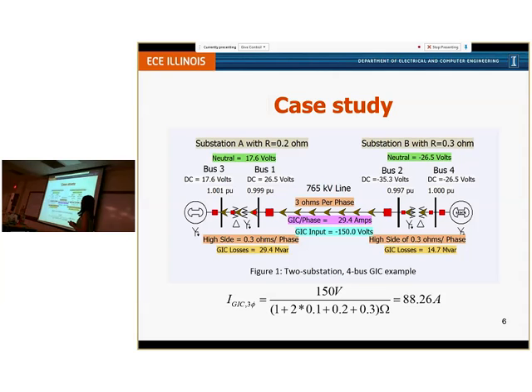Let's look at a case study for this. This is a two-substation, four-bus system, and the geomagnetic disturbance creates an electric field of 1 volt, in this case 1 volt per kilometer. The two substations are separated by 150 kilometers. Hence, the voltage difference is 150 volts. The grounding resistance of substation A is 0.2 ohm, and the grounding resistance of substation B is 0.3 ohm.